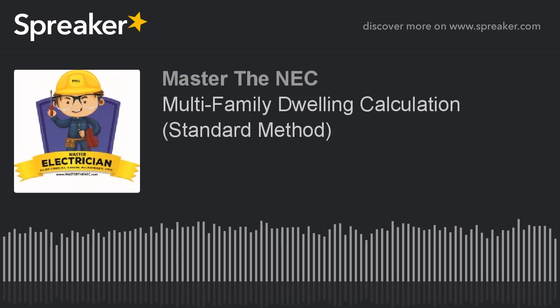So under the service column, we're going to take the heat or the air conditioning. We get to omit one of them. We take the larger, so we write down 81,000. So that goes under our service column. Now, under the neutral column, this is purely 240 volt loads. Both of them were, so there is nothing to write under that column. Okay? Now let's move on.